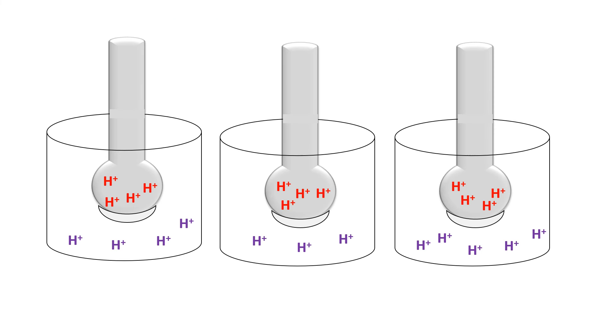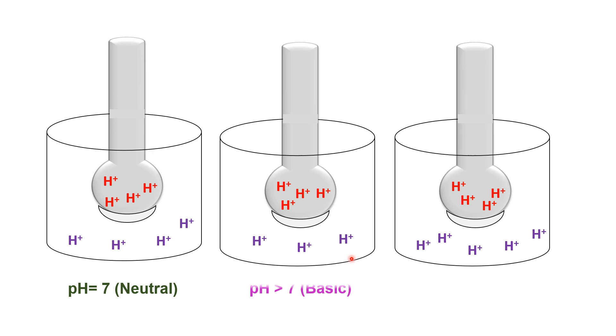How does a pH electrode record a solution as acidic, basic, or neutral? The hydrogen ion concentration inside the probe has a fixed value, while the external solution has a variable hydrogen ion concentration. If the number of hydrogen ions inside the probe equals those outside, the solution is recorded as neutral with pH 7. If the number of hydrogen ions inside the probe is greater than outside, the solution is recorded as basic with pH greater than 7.